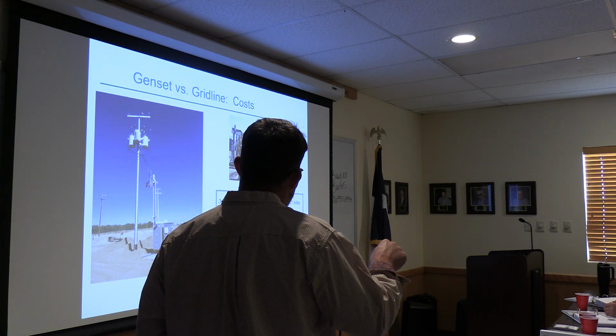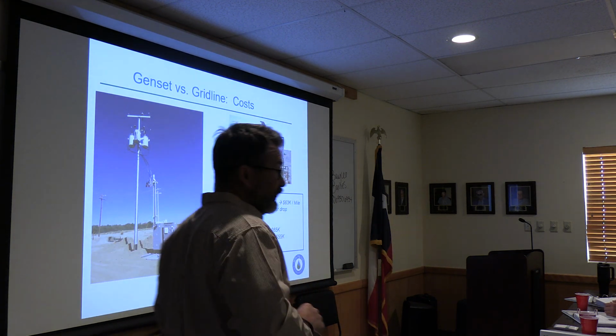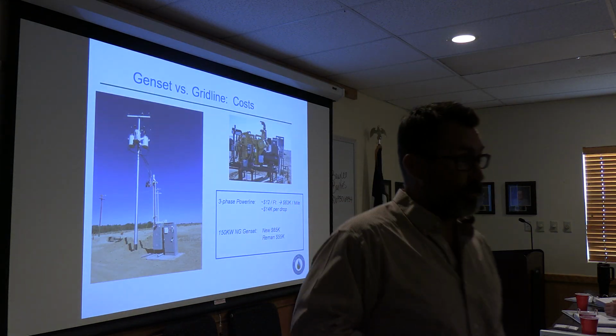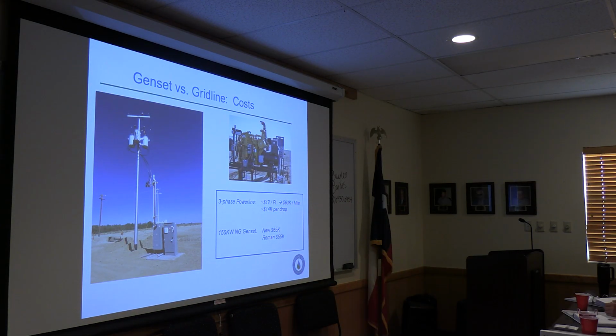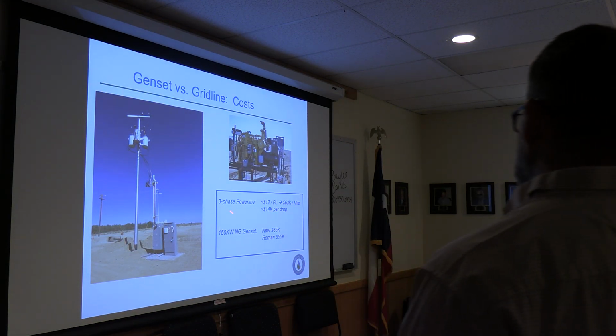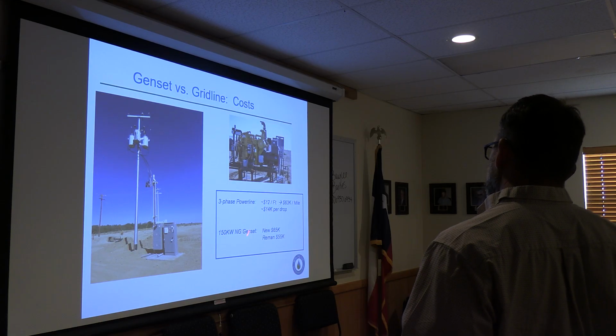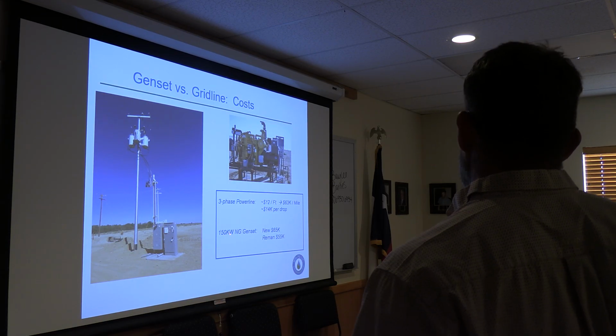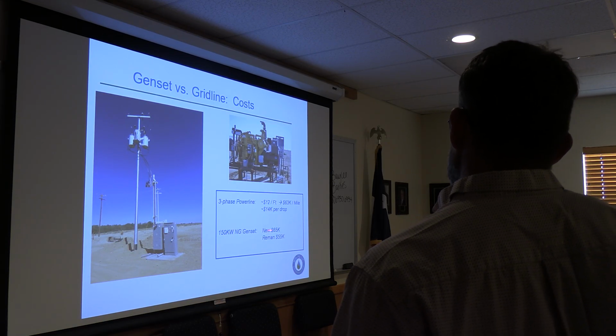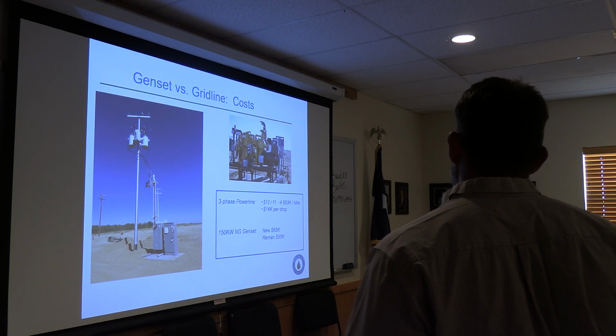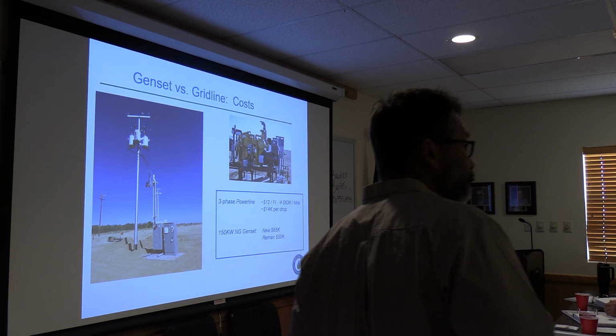You're going to be in the mid $60,000 per mile to run it, and about $14,000 per drop. That's real money. Your gen set's not going to be free either if you do it right. You're probably going to be on a 150 kilowatt gen set, something like a 200 horse unit. New at 65K, reman at 55K. You're going to have some real money in that too.